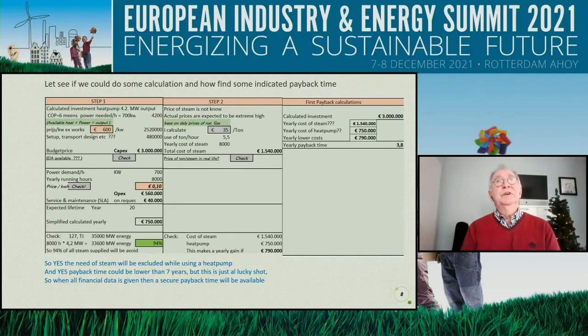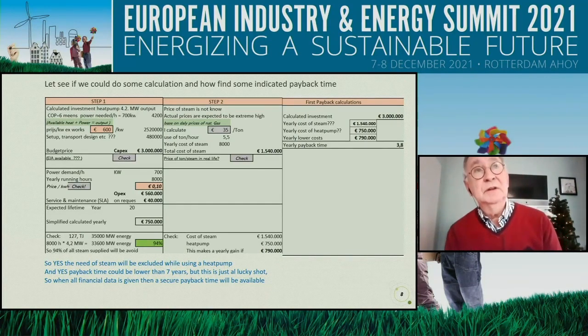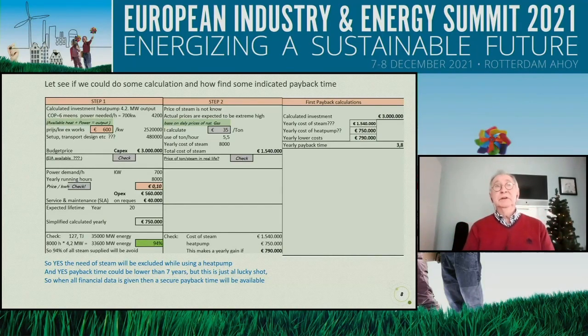And that's rather simple why: because the lift between the lowest temperature and the highest temperature at the source and sink side is very small. That makes it very easy for a heat pump that is able to use higher temperatures. Because it's only, let's say, 30, 35 degrees to lift—sorry, 45—that makes it possible to have a very high COP. And when you compare it to heat pumps in houses etc., don't forget the temperature all year long is the same continuously, so it cannot be compared to a heat pump in houses.